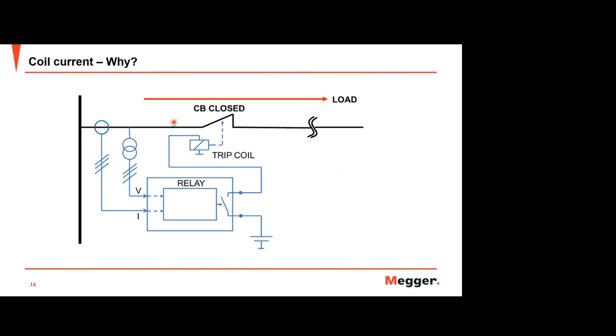As you know, in an electrical system like this, when the CB or circuit breaker is closed, you can see the CT and VT and the relay. As you know, the relay here is like the human brain, and the circuit breaker is like the human muscle. So the breaker will operate based on the order from this relay. Of course, the relay will operate based on the condition of input voltage or current. So when the system is normal like this, current flows to the system, the CB is still closed, and the relay contact is still open.